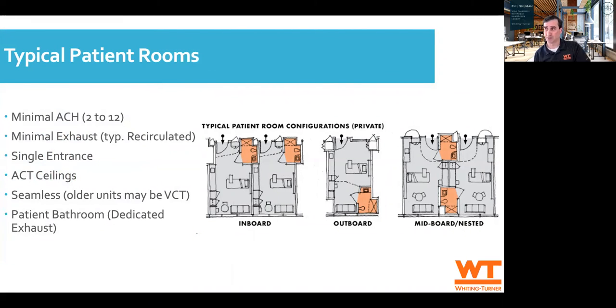I've taken a couple typical patient rooms that could be found in any hospital. For the purpose of this analysis, I've assumed there is a patient bathroom, and that's where the exhaust is. Other things you'd find within these typical patient rooms: a lot of times you have a very minimal air change, I think the requirement's around 100 CFM makeup air into the unit, and then you have the bathroom that's exhausting. So you may have anywhere between 2 to 12 air changes per hour.